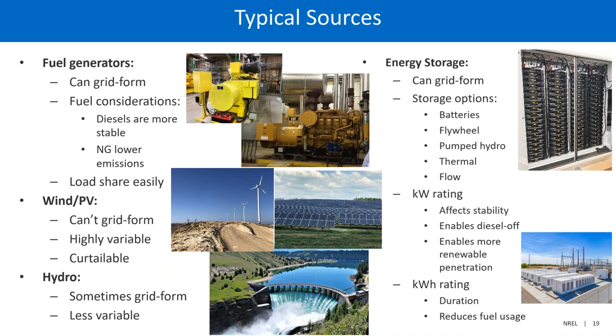Diving into sources a little more—most of these I've already mentioned. Fuel generators can grid form, meaning they can produce their own voltage and don't need another source to do that for them. Typically diesels are a bit more stable, although natural gas generators have lower emissions, so it depends on the end state and what's required. They share load really easily between themselves because it's a fairly well-developed technology.